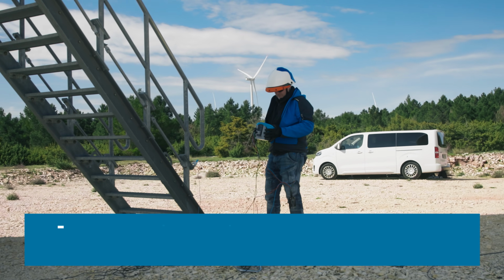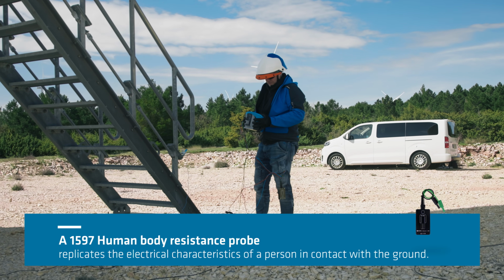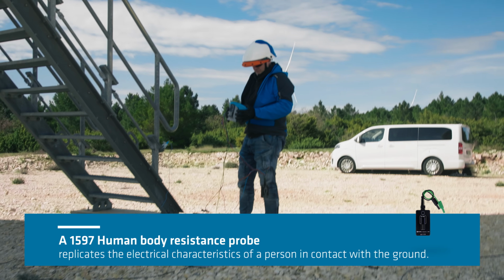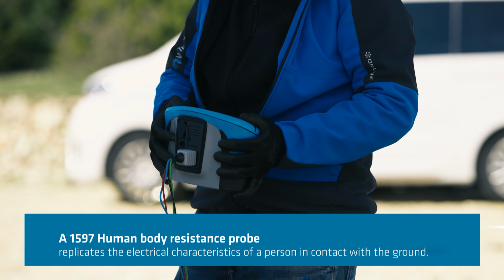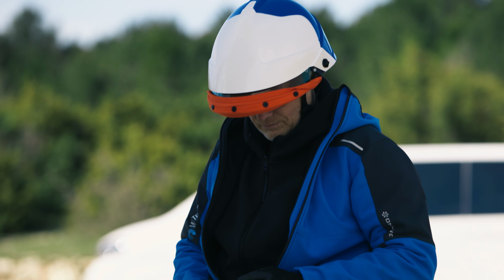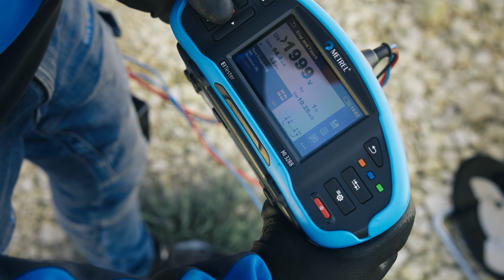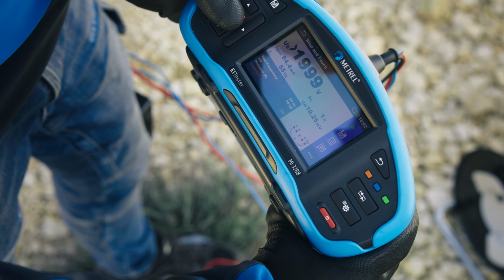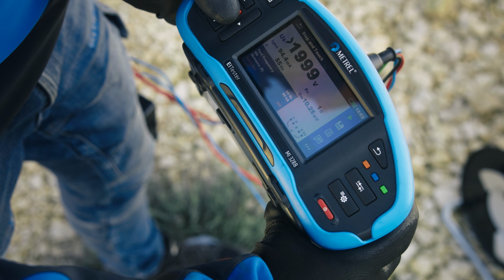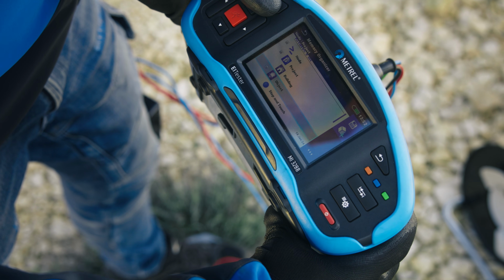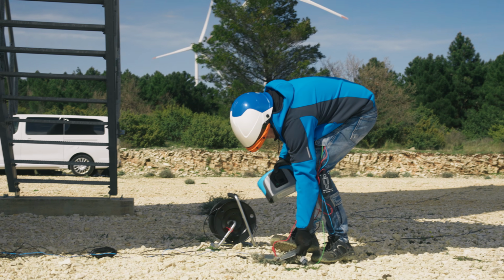These measurements are performed with the help of 2 200 square centimeter metal plates and a human body resistance simulator, which replicates the electrical characteristics of a person in contact with the ground. This setup ensures that the results reflect the worst-case scenario, such as a lightning strike, and allow for accurate calculations of the potential impact on human safety.